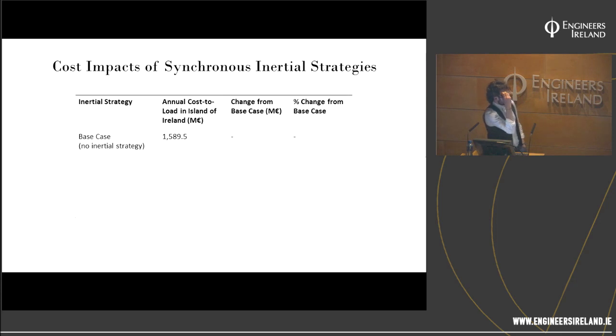And then quickly go to, again, you don't need to worry about the cost numbers here. So what we've done is we've just compared different inertial strategies for a high wind power system. So there's the cost if you've no inertia. If you do what I said at the start and you say, okay, I want 8 generators online at all times, obviously there's going to be times where there's less than 8 units online, and then you have to constrain those units on, so your costs are going to increase.